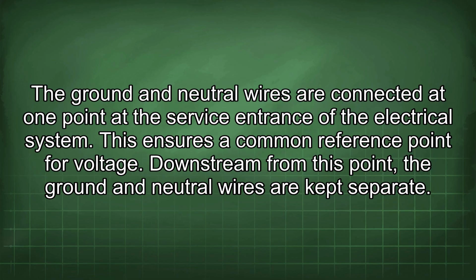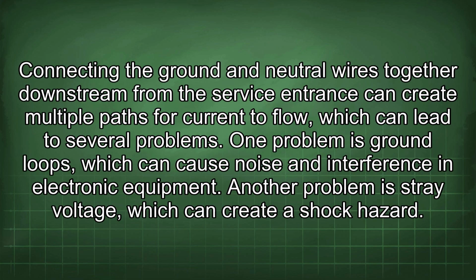The ground and neutral wires are connected at one point at the service entrance of the electrical system. This ensures a common reference point for voltage. Downstream from this point, the ground and neutral wires are kept separate. Connecting the ground and neutral wires together downstream from the service entrance can create multiple paths for current to flow, which can lead to several problems.